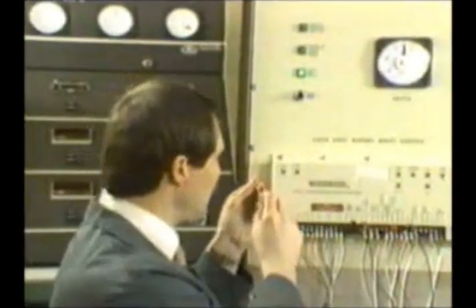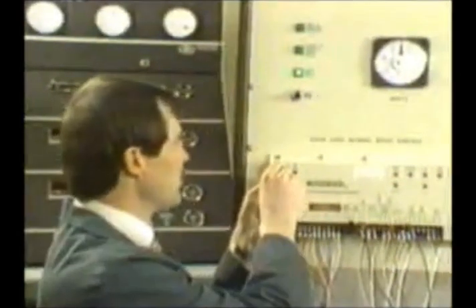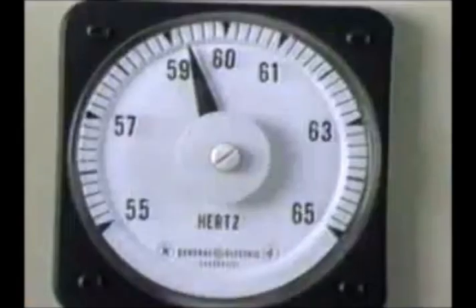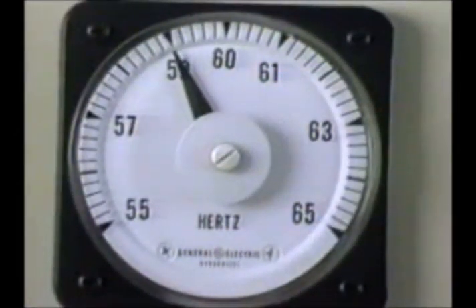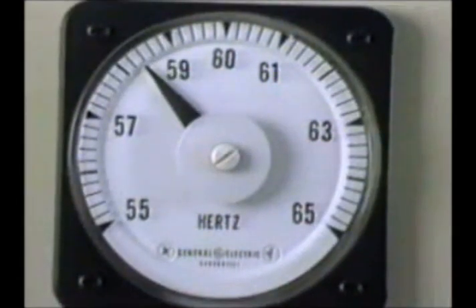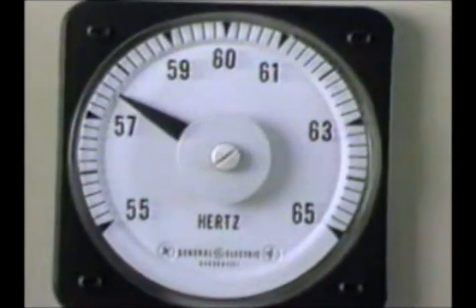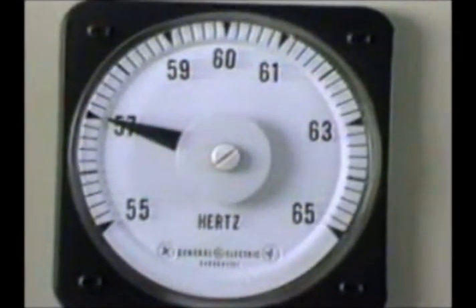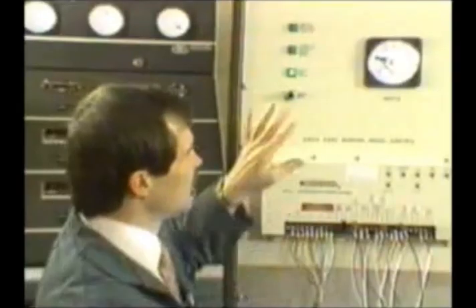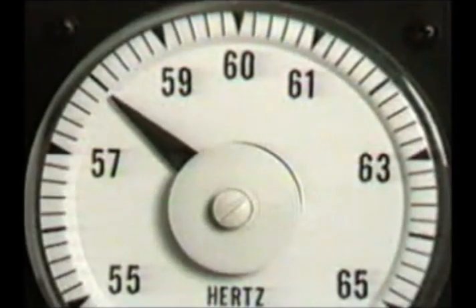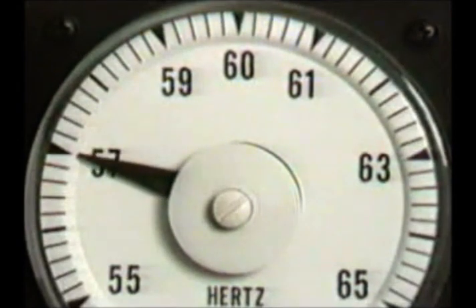And you'll see if you watch your Hertz meter, as I start turning my droop potentiometer clockwise, we're going to decrease in speed. So I'm going to go ahead and set my droop up for 57 Hertz. So now my droop is set up for 57 Hertz when I'm at full load. So let me start taking load off, and you'll see we'll start increasing in speed. I put it back on, we come back down to the speed.